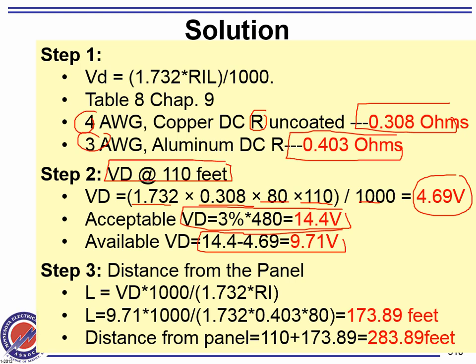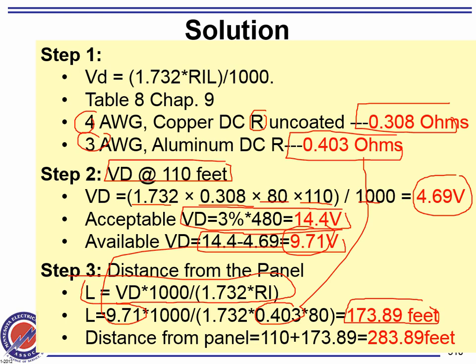Now you find the length. You can see here's my length? Flip the formula. Can you guys see this number? That number, you flip it and put it in the length here, times 1000. Here's the new impedance for aluminum. That will get you how many feet? 173.89. Now, that's how far you can go from the original location.